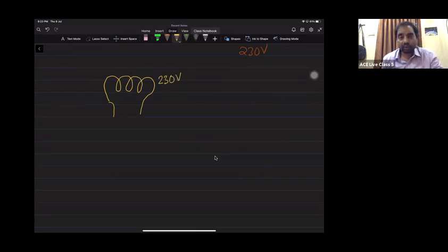Right. See, now here I'm just designing the output of this generator. So in this generator, I'm having 23 turns. Then the voltage it can give is 230 volts. Whatever coil I have designed, those windings have the capacity to withstand a safe current of 1 ampere. The winding size and other things we have designed like this. So this generator can give an output at 230 volts when you are loading the generator with a current of 1 ampere, and we call this the output rating.